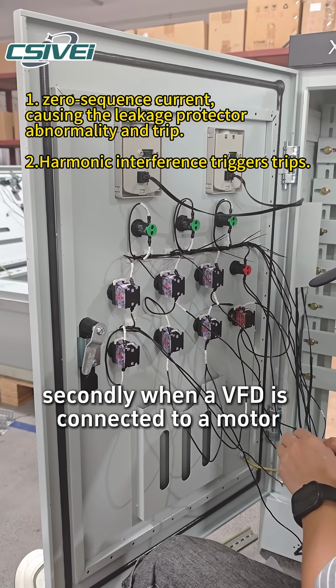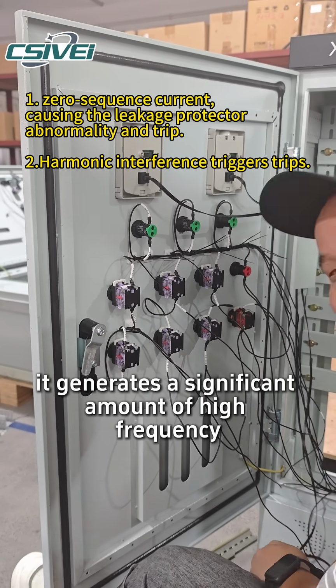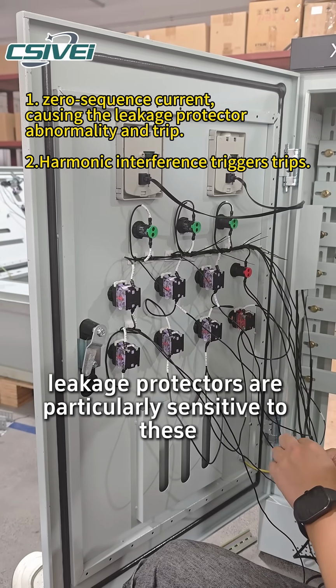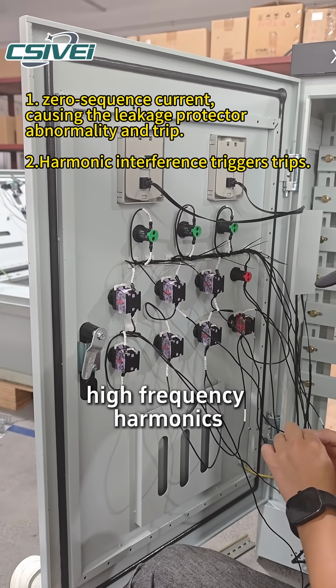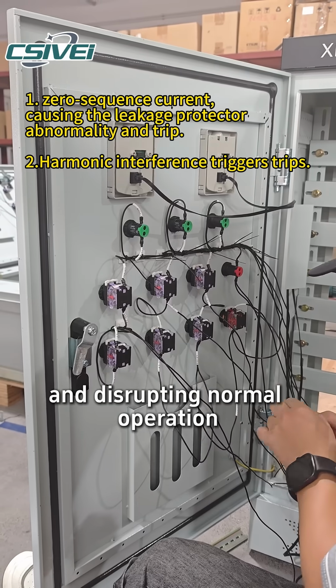Secondly, when a VFD is connected to a motor, it generates a significant amount of high-frequency harmonics. Leakage protectors are particularly sensitive to these high-frequency harmonics, leading to false tripping and disrupting normal operation.